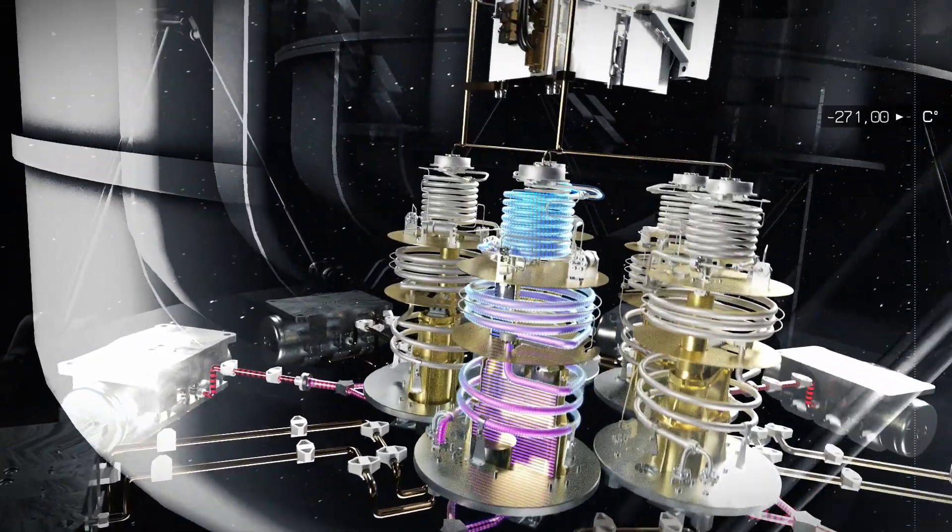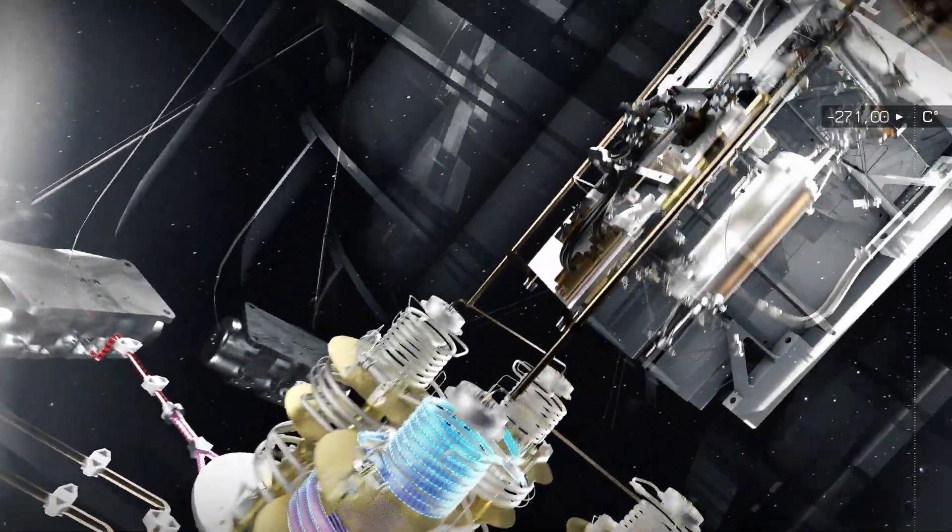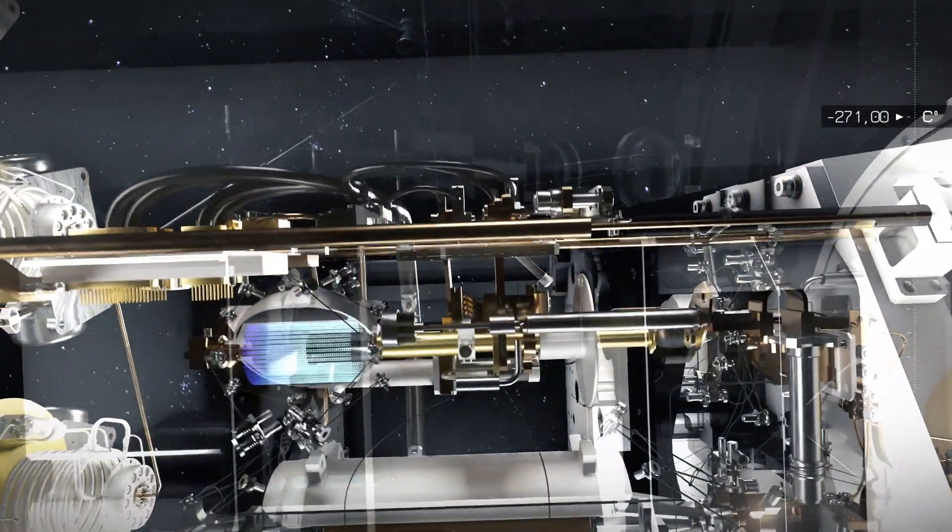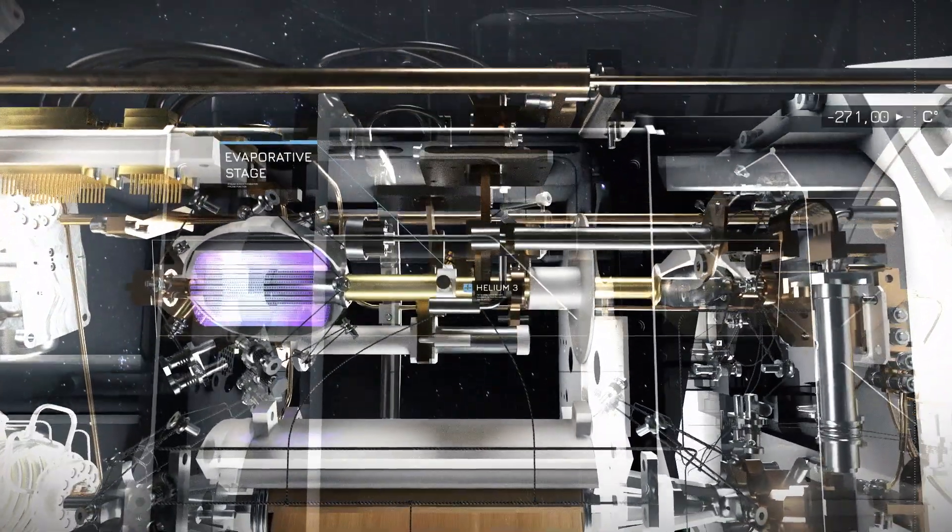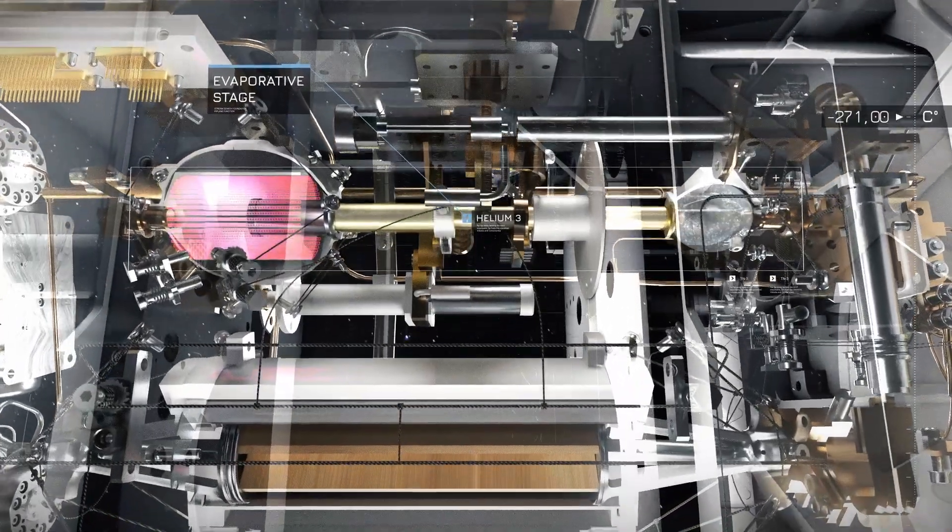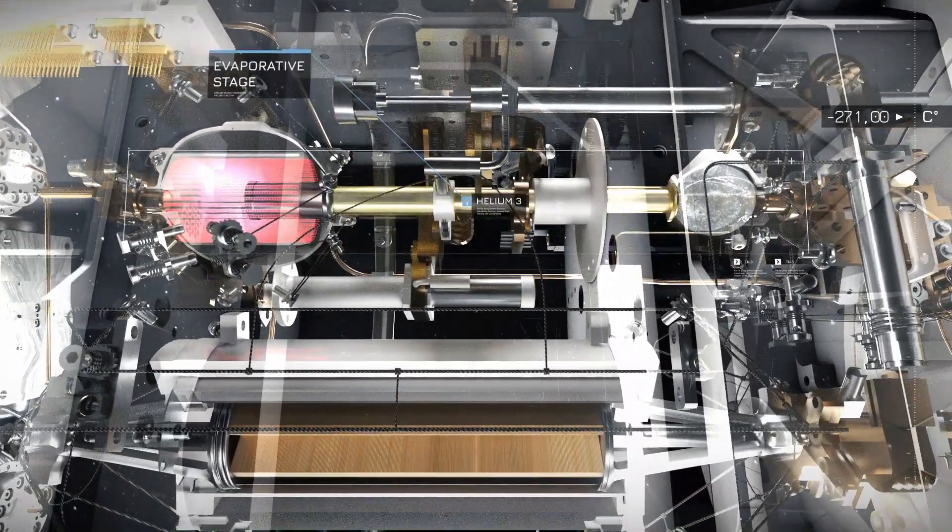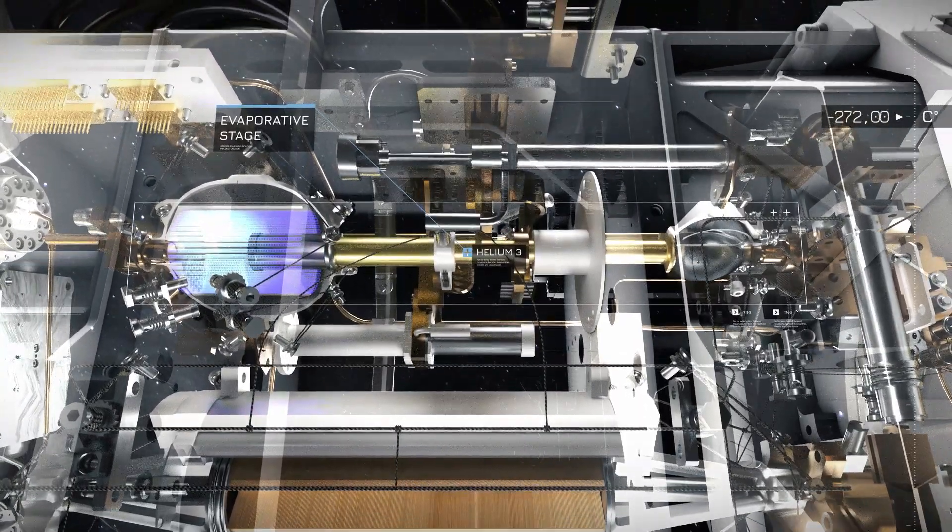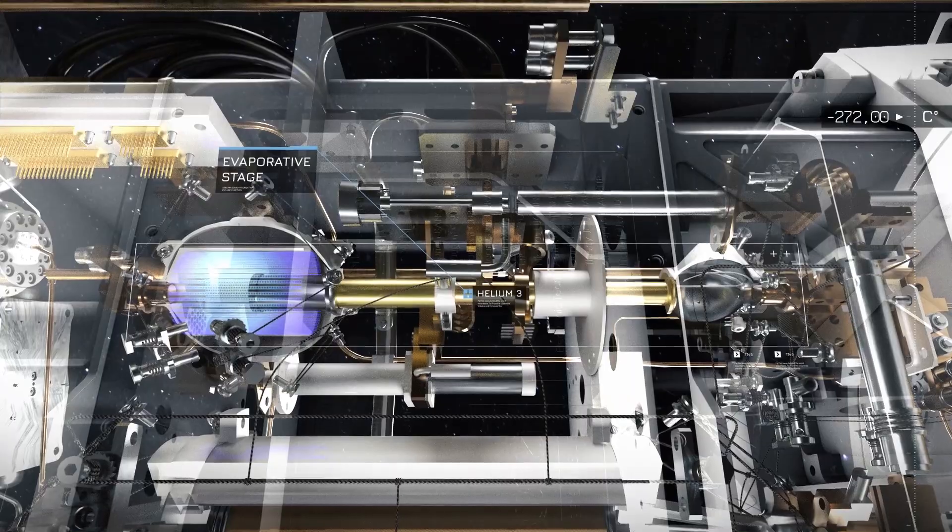Further decreasing the temperature by a couple more degrees is a major challenge. It is done by the two steps of the hybrid sub-Kelvin cooler. The evaporative stage works in the same way as we cool off by perspiration. As the liquid helium evaporates, the temperature is lowered still further.